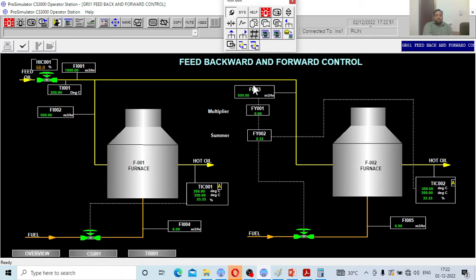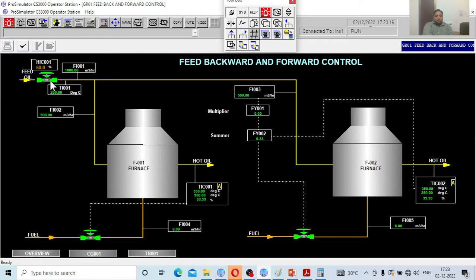Let me understand the objective of the present control. Oil is going into the furnace, getting heated up through the heating coil, and exits the furnace. This happens the same way in both furnaces. The objective is to maintain the exit oil temperature. The set value is 350 and the process value is also 350 at present, so there is no control action. When I disturb the system, both controllers will take action. The left side is feedback, and the right side is feedback plus feedforward — which one reacts faster is the objective.